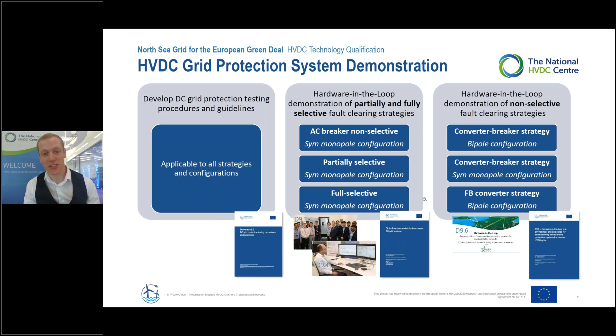The key takeaways from us are that we demonstrated successful operation of fully, partially, and non-selective protection schemes on the most realistic test cases we could come up with about installation on a real power system. The main thing is the IEDs we tested are expected to be sufficient for potential future HVDC grids. We evaluated interoperability of these protection devices, demonstrating that a multi-vendor protection system could be achievable, including the use of IEC 61850 in some cases.